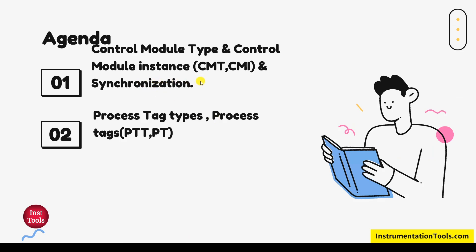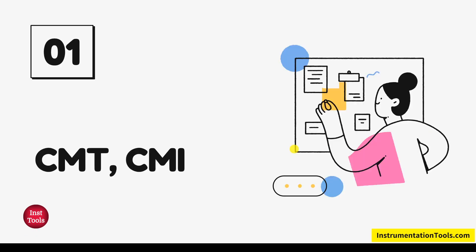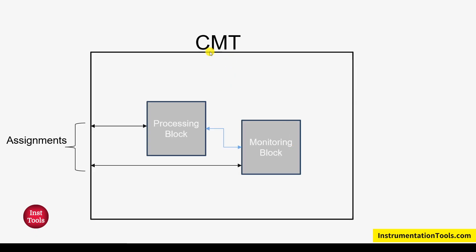Our agenda: control module type, control module instance, and synchronization. CMT is nothing but a CFC plane consisting of a number of FBs to satisfy one operation. For example, here you can see a CFC plane with a processing block and a monitoring block — these are FB instances. These two blocks may have interactions between them, and to communicate with the outside world — for example, with other charts, memory variables, or directly to the IO addresses — we use a concept called assignments.